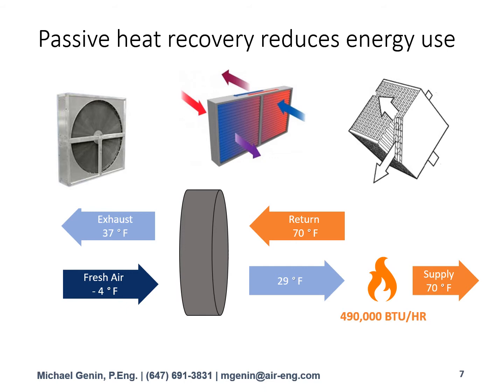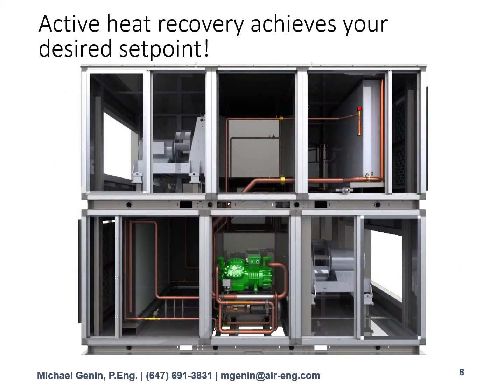So to go beyond this level of efficiency, we really need to take advantage of the exhaust. And what's happening here is the exhaust is still 37 Fahrenheit. So to go beyond this technology, we need to extract more energy from that exhaust to break the barrier that limits traditional passive heat recovery. So what active heat recovery does is uses a refrigeration system.